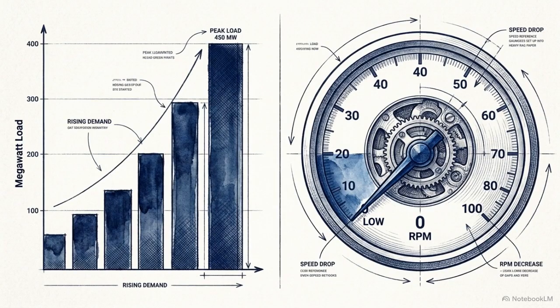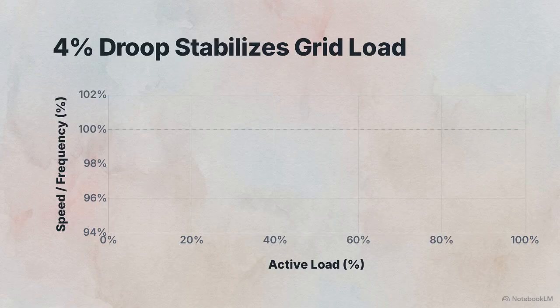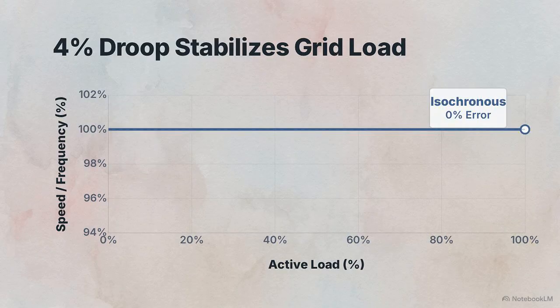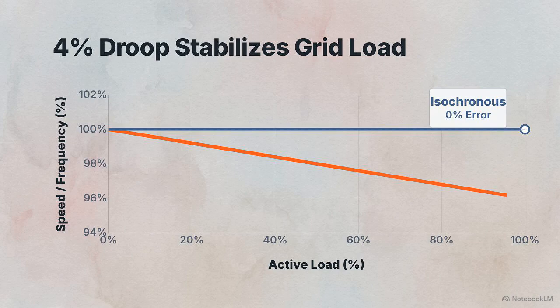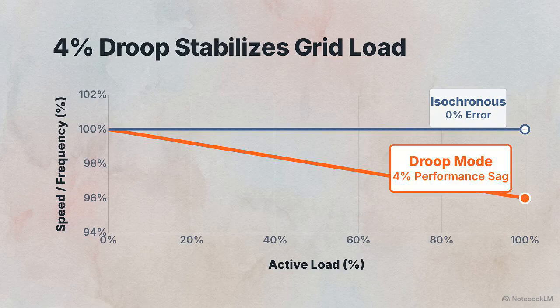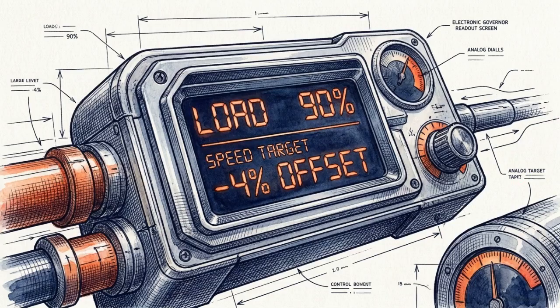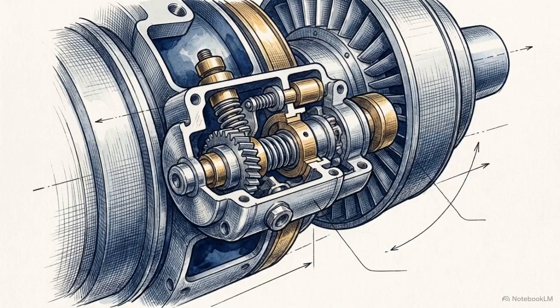Plotting speed against active load, this perfectly flat line at 100% speed represents isochronous control, maintaining zero steady-state error. Watch the Droop curve. As load climbs to 100%, speed drops steadily to 96%, demonstrating the intentional performance sag. As load increases, the governor allows a typical 3 to 5% speed sag. It stops continuously fighting to maintain exactly 100%.